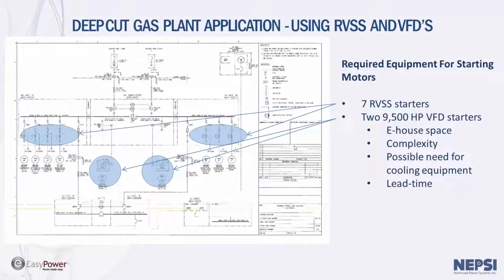The actiVAR can also be used on a plant-wide basis. Here's an example of the actiVAR being used on a plant-wide basis. We have a deep cut gas plant here, which consists of 7 soft starts. You have 4 here, plus 3 over here, so a total of 7 soft starts spread on 2 different buses. And we also have 2 VFD drives. Those VFD drives are set up to start 2 9,500 horsepower motors. These will all be placed inside an e-house. The drives may require some cooling equipment, and there's of course the lead time issues that you commonly have with VFD drives. They tend to have longer lead times.